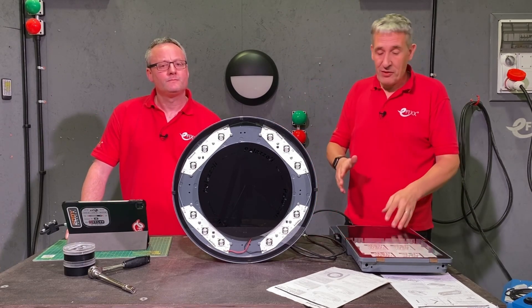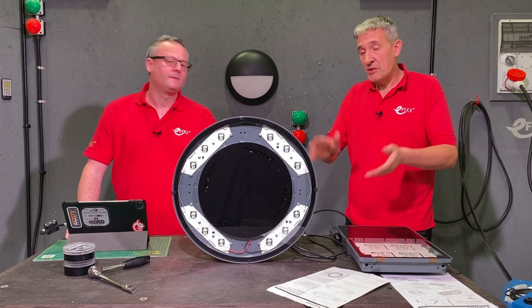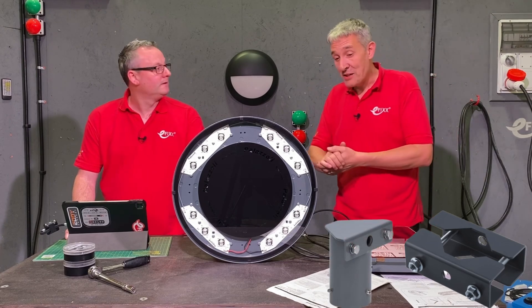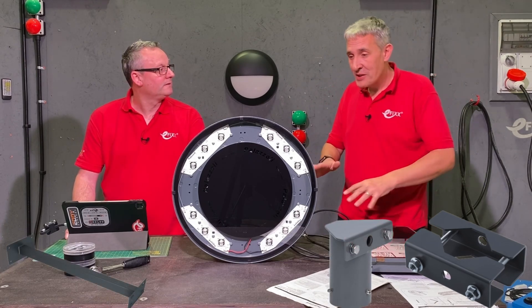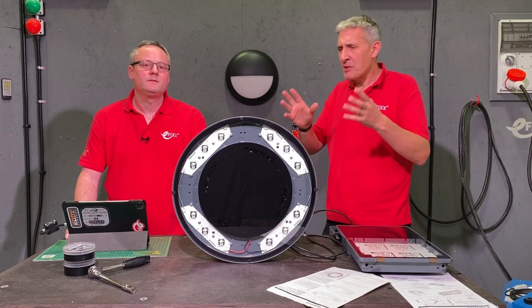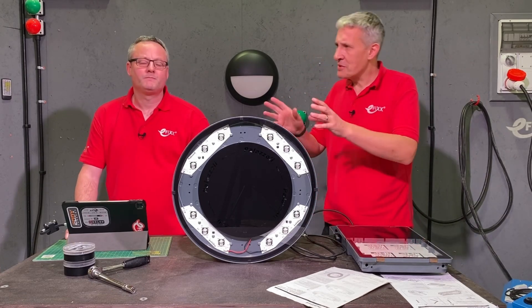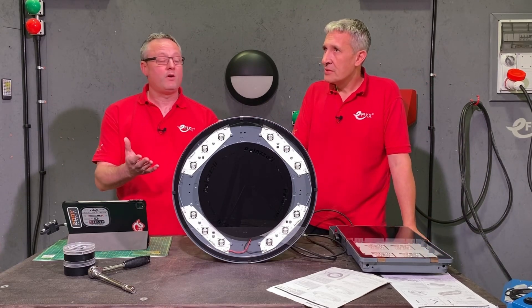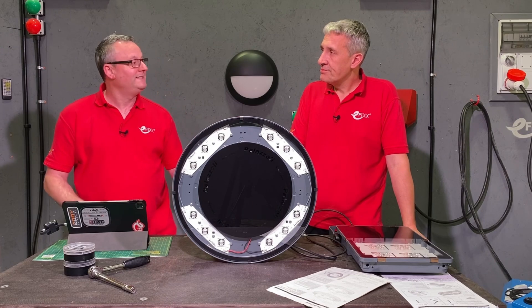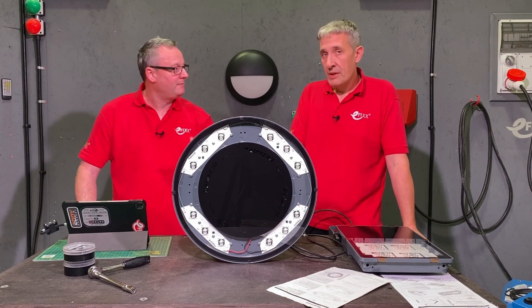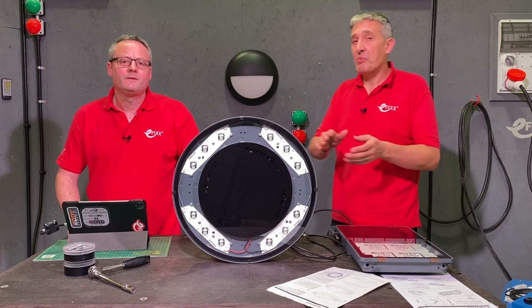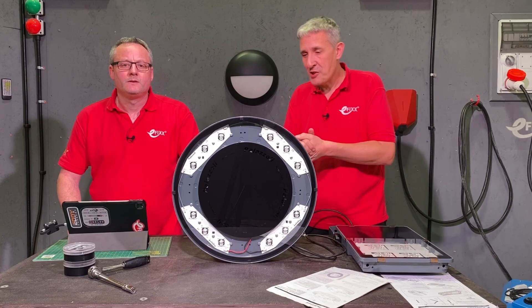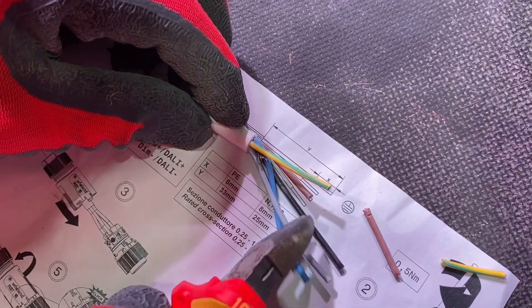Or you can even configure this as a floodlighting option. And to go with that, there are mounting poles. You can mount it on a pole, on the top of a pole. There's other options. Wire guards. And then think about the other materials. So this one here has got glass. But what's the other option, Gary? You can have plastic as well. If you think you're maybe in a food processing environment, you probably wouldn't want a glass lens in that environment in case, for some reason, it happened to shatter and obviously came down. So there is a specific approval for that if you're working in the food industry. You don't want glass shattering. And that can cause the shutdown of an entire factory.